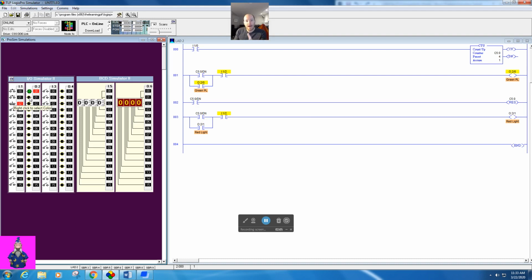Well, why? It's about how the PLC scans. Because what happens is when this goes done for that split second, it comes down here, turns on for one scan, okay? This activates. This locks in the memory. Then the done bit goes true, resets it, then it comes down here. This has now gone false, okay? And so what that does is that creates an issue where this will never turn on. This will never have the ability to turn on. So let me show you how we solve that problem, and then I'll show you how we solve this one.